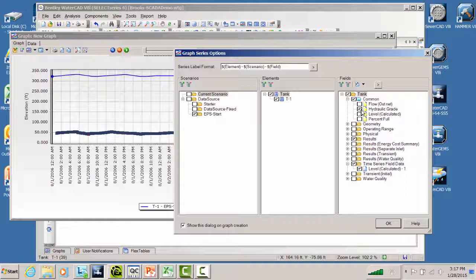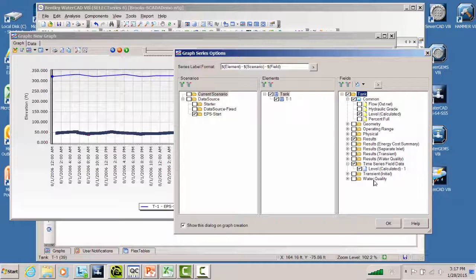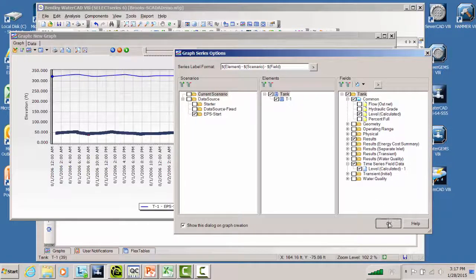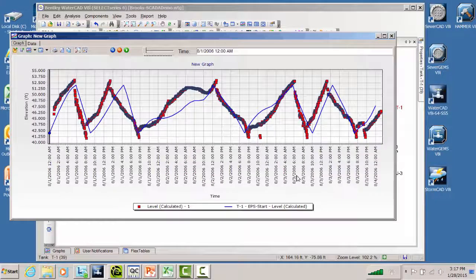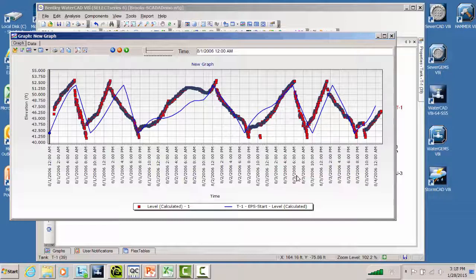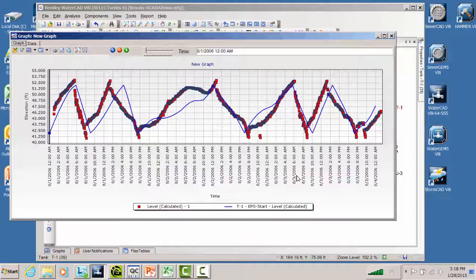Well, they're different to the datum that I was using. So I'll get rid of hydraulic grade line and convert that to level. And by doing so, I see I have a reasonable agreement here of the tank levels going up and down. It's really hard to get time shifts exactly right. Usually, while the absolute values or numerical values look pretty good, times are going to change because if your model was done assuming one particular pattern for a day and no two days are ever exactly alike, you're going to have pumps coming on at slightly different times. That's what you see in these little time shifts that we have here. But overall, the model looks pretty good as far as comparing it with the field data in this particular case.